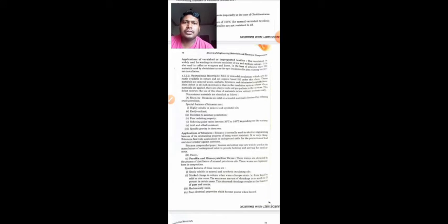The features of bitumen: highly soluble in mineral and synthetic oils, easily oxidized, resistance to moisture penetration, but poor insulating property. Softening point varies from 30 degrees centigrade to 140 degrees centigrade depending upon the variety or type of bitumen which you have selected.